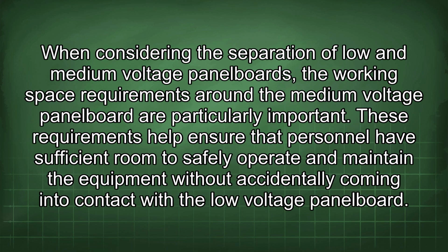When considering the separation of low and medium voltage panel boards, the working space requirements around the medium voltage panel board are particularly important. These requirements help ensure that personnel have sufficient room to safely operate and maintain the equipment without accidentally coming into contact with the low voltage panel board.